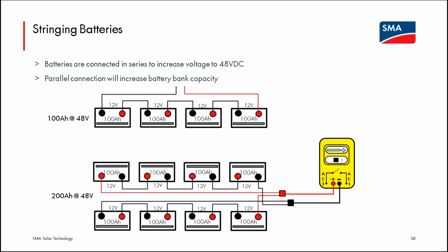Most lead acid batteries you're going to find in 12 volt or smaller monolithic units, and you need to wire those in series so that the series adds up to 48 volts. Most 12 volt batteries you're going to find in lower capacity. If you want to get to larger amp hour capacity, you're going to be going down into the 2 volt range, and then that's 24 batteries in series to get that 48 volt. Once you have the maximum capacity in a string, the only way, if you want to add more amp hours, is putting strings in parallel.